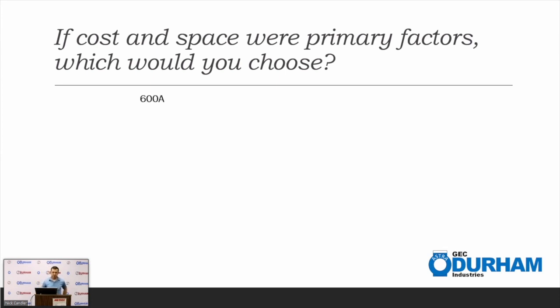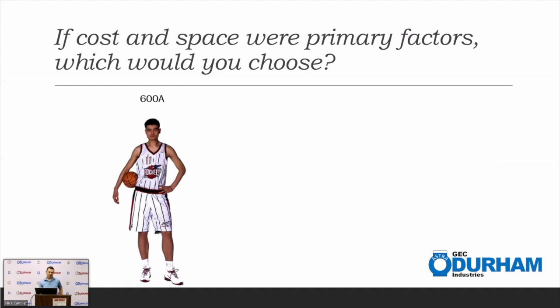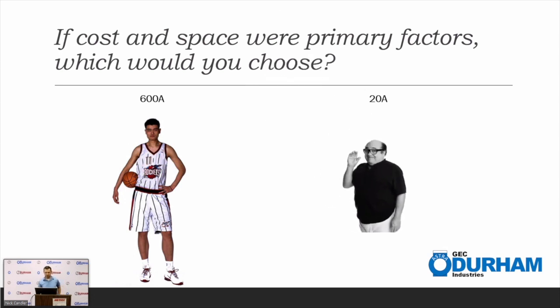We have a 600 amp service. We could have an NBA sized meter socket on the side of the utility. Wouldn't be very good for a pole mounted application either. But if we were to bring in a little 20 amp, yeah, much less costly and obviously much smaller.